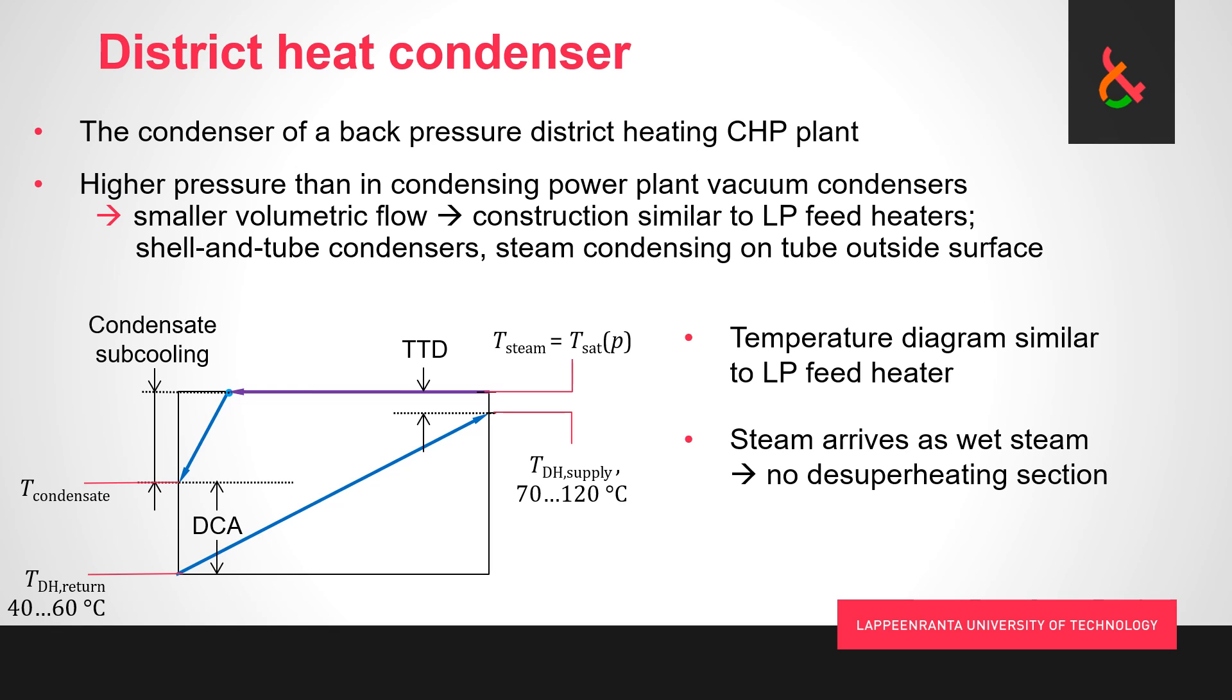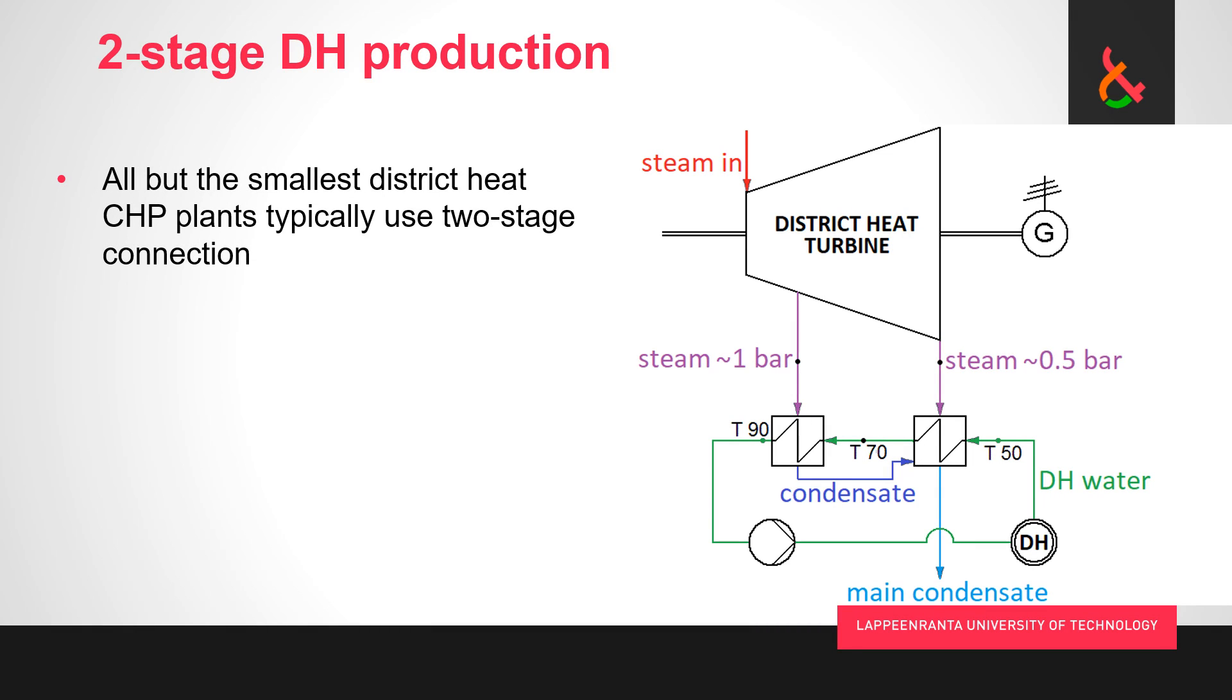Now let's look at two-stage district heating production. Here we have a diagram of how it's implemented. This is something we have almost always implemented in all but the very smallest cogeneration plants producing district heat. The idea is that we have basically two condensers in series. First we heat the water halfway, and only then we take extraction steam and heat it all the way up.